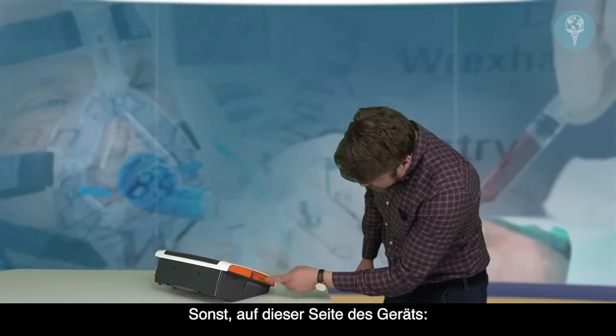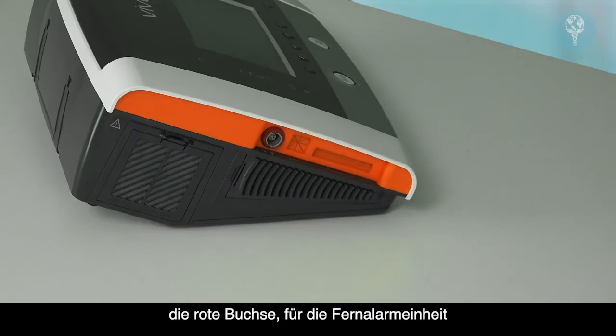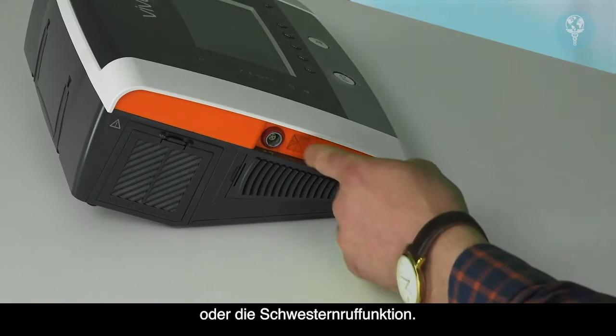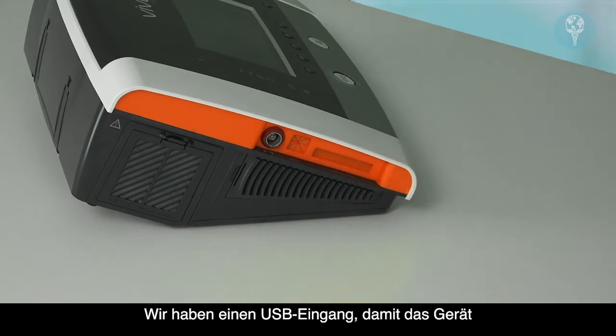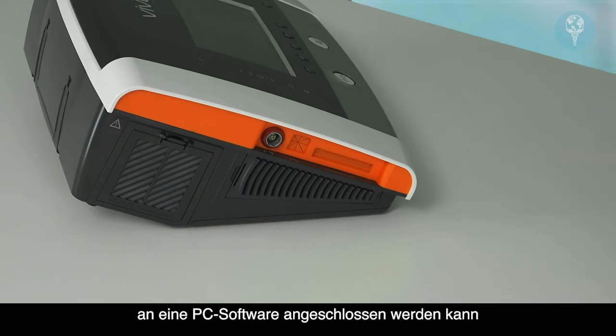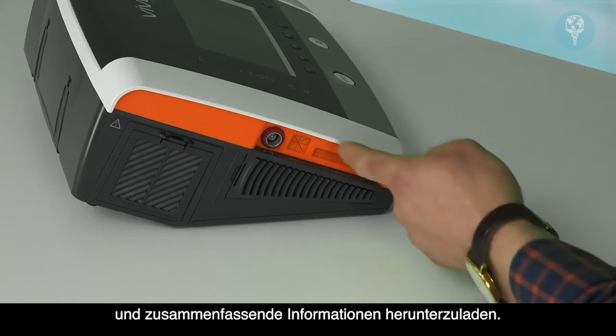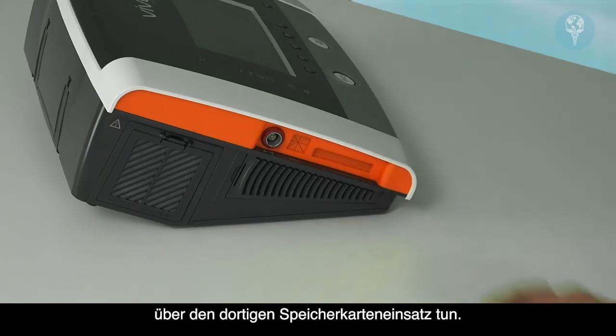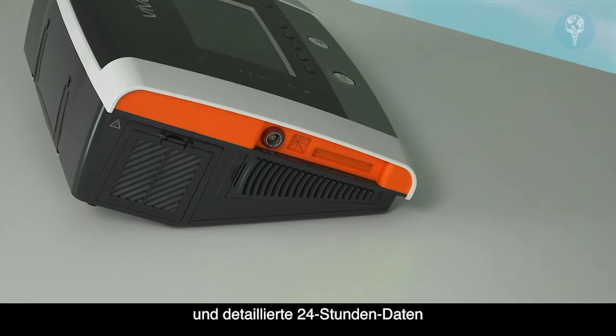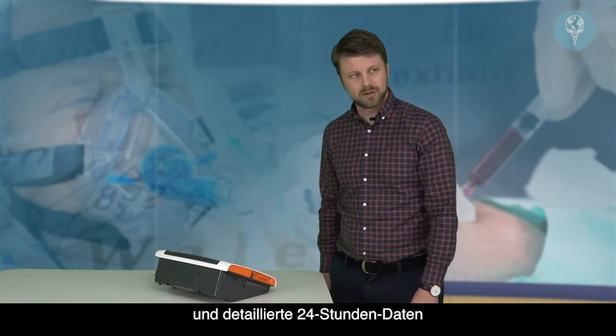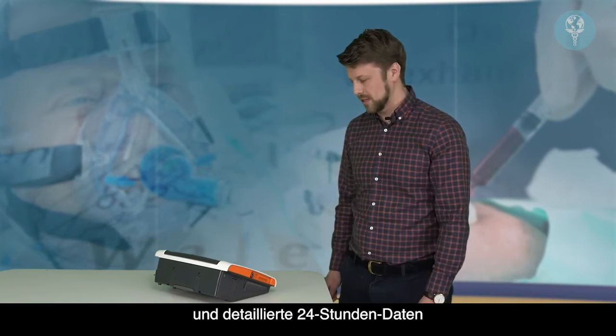Rest of the side of the device, so the red inlet is for a remote alarm unit or a nurse call adapter function. We have a USB input, so the device can be plugged into a PC software platform, and we can live view patient data and download summary information. And we can also do that via the memory card insert there, so you can look at summary information and detailed 24-hour data on the PC software that way as well.